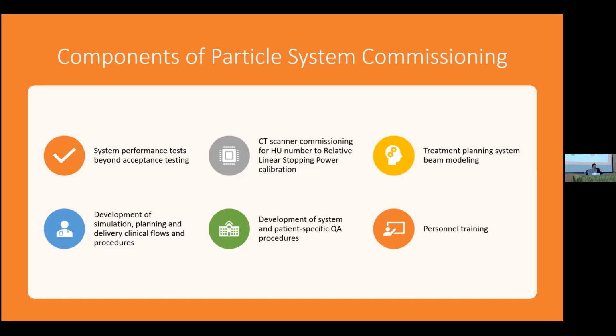And then there's the acceptance test. That's where we go and test all these things that the vendor says is supposed to work a certain way, and we're checking, making sure it's actually working that way, so we are sure that they're delivering what was promised. And that's the acceptance test. And then there's the clinical commissioning. So the technical commissioning that the vendor is doing, making sure it's operating to specification, is different than the things we need for the clinical portion. So there's data, there's information we need in the clinical commissioning so that we can treat a patient effectively and put into the treatment planning system and these other things that aren't necessarily part of the technical commissioning.